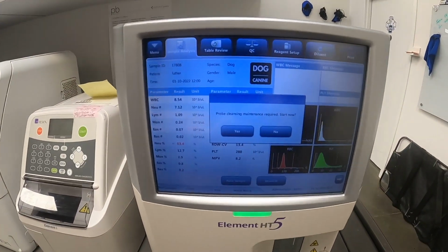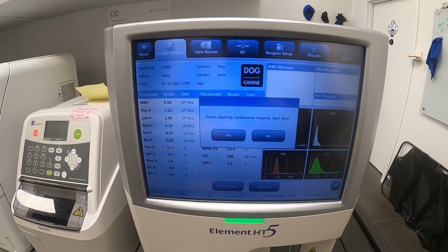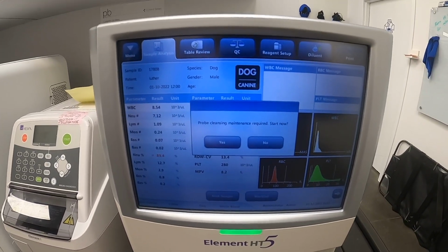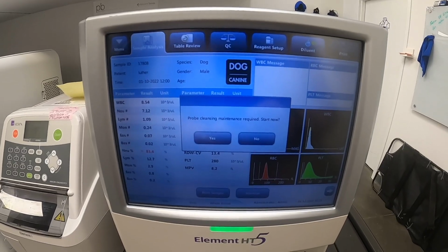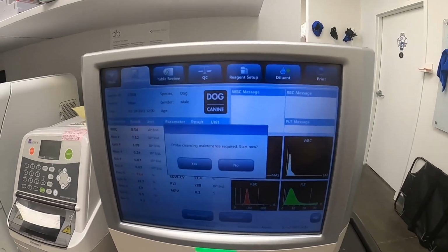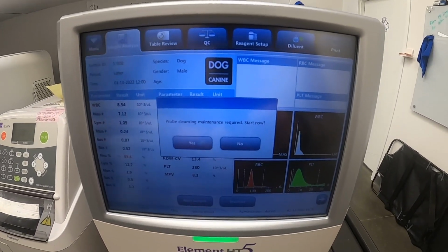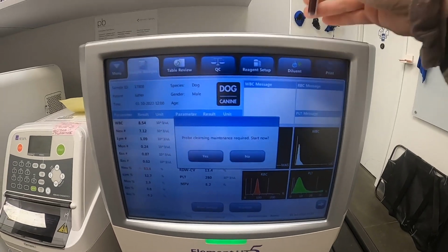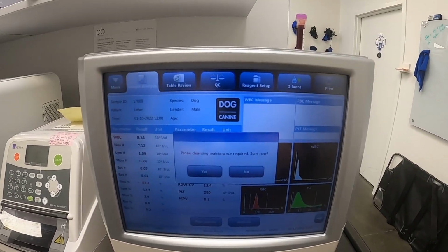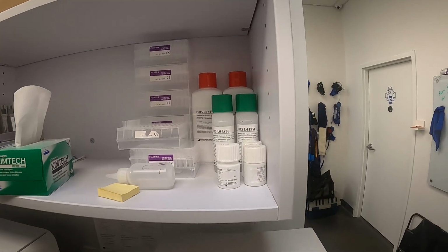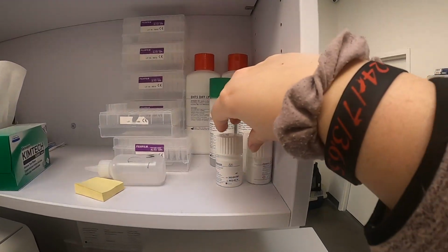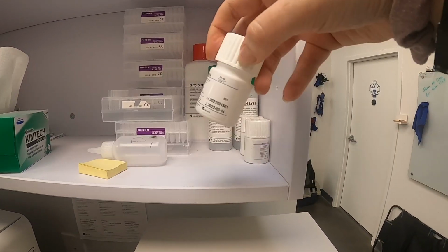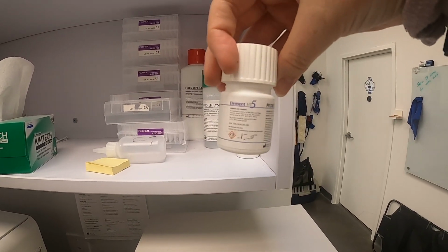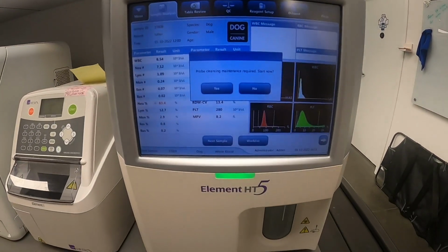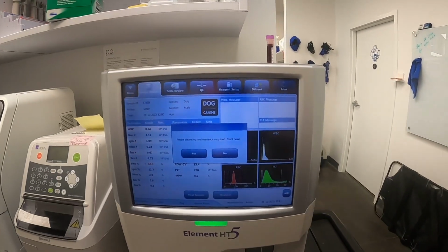Okay. So once we're out of standby mode, we have this message that pops up that says probe cleaning maintenance required. This is a maintenance step that is required to do daily, so every 24 hours on this machine. So I can show you how to run that. Our probe cleanser fluid are in these little small jars here that say probe cleanser. So to perform this, we're going to hit yes.